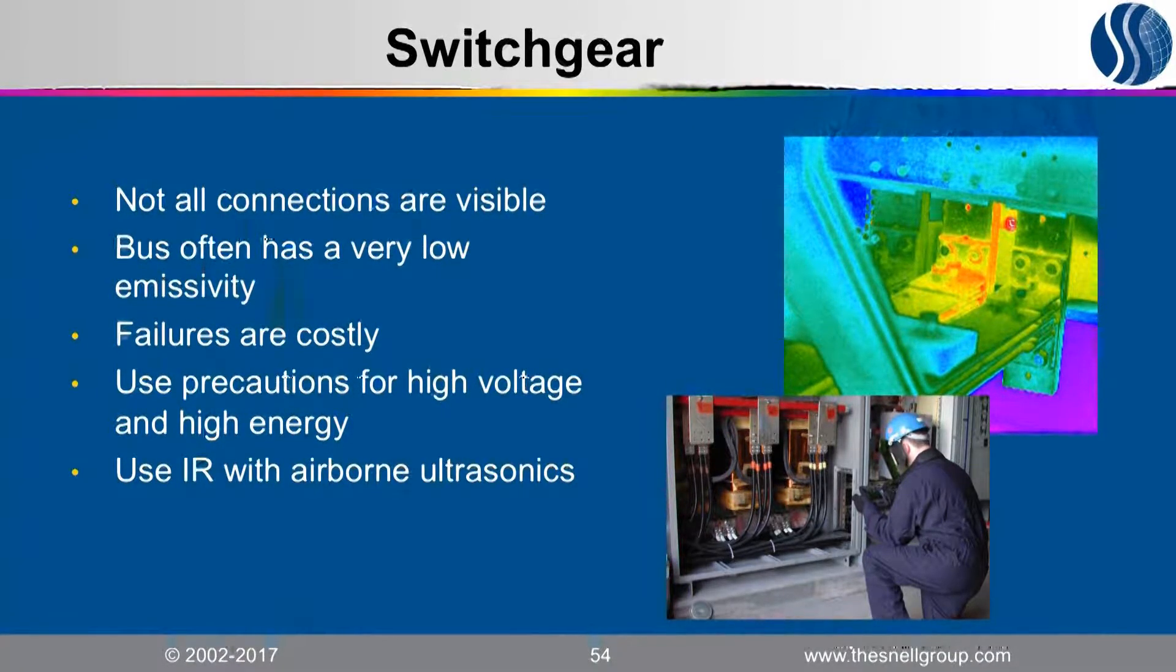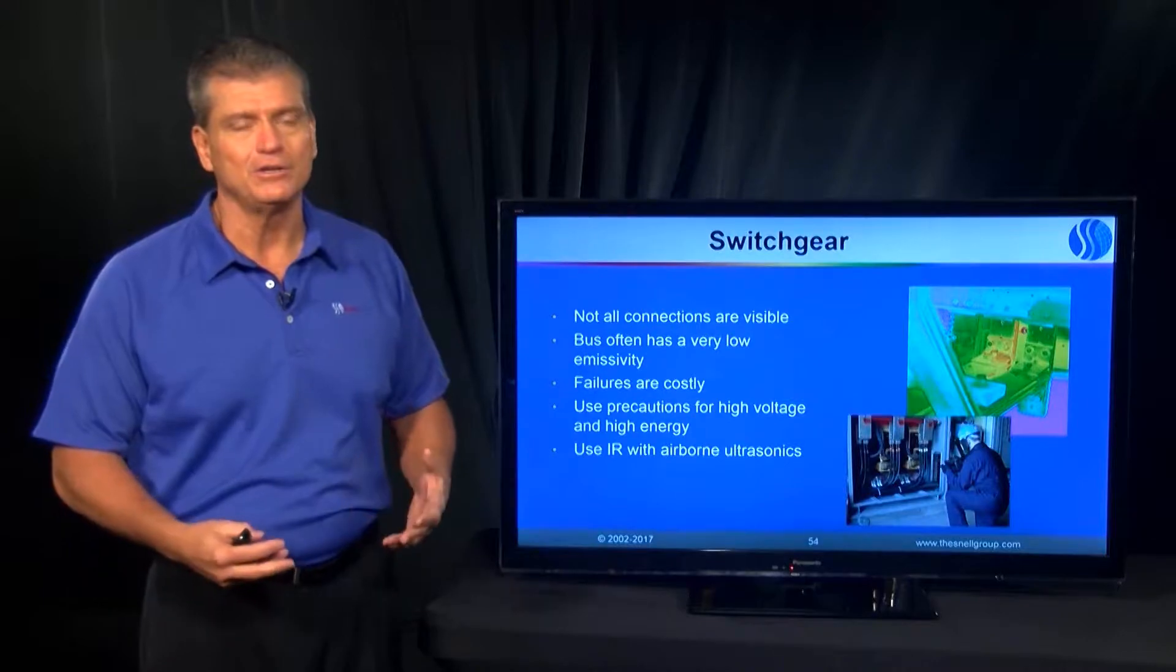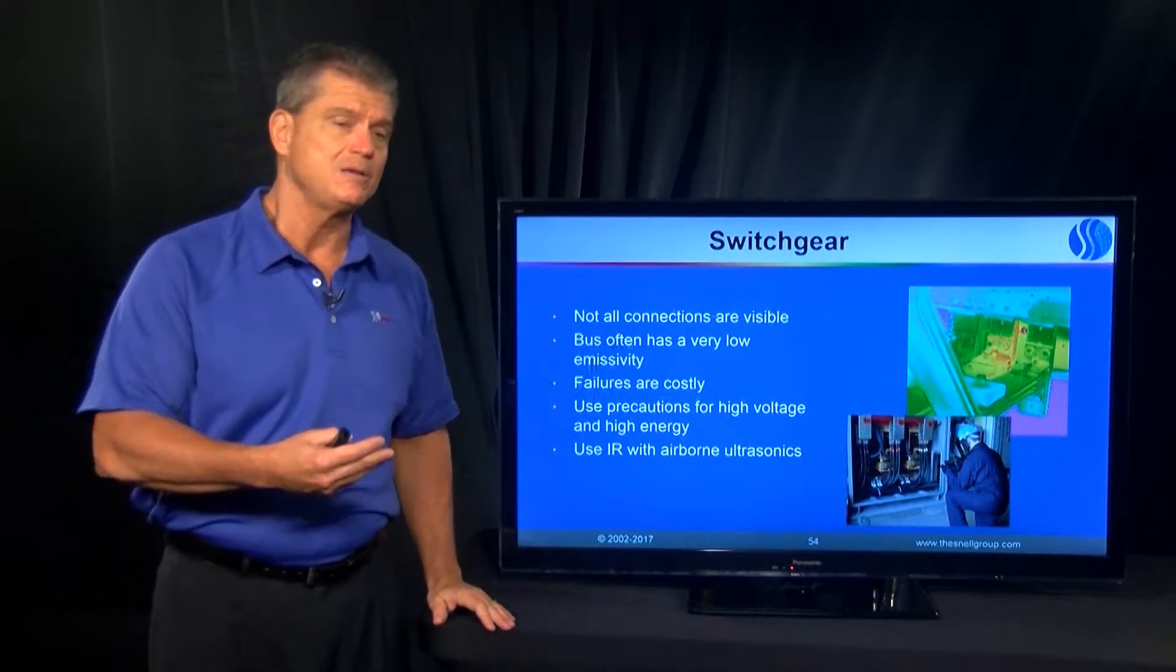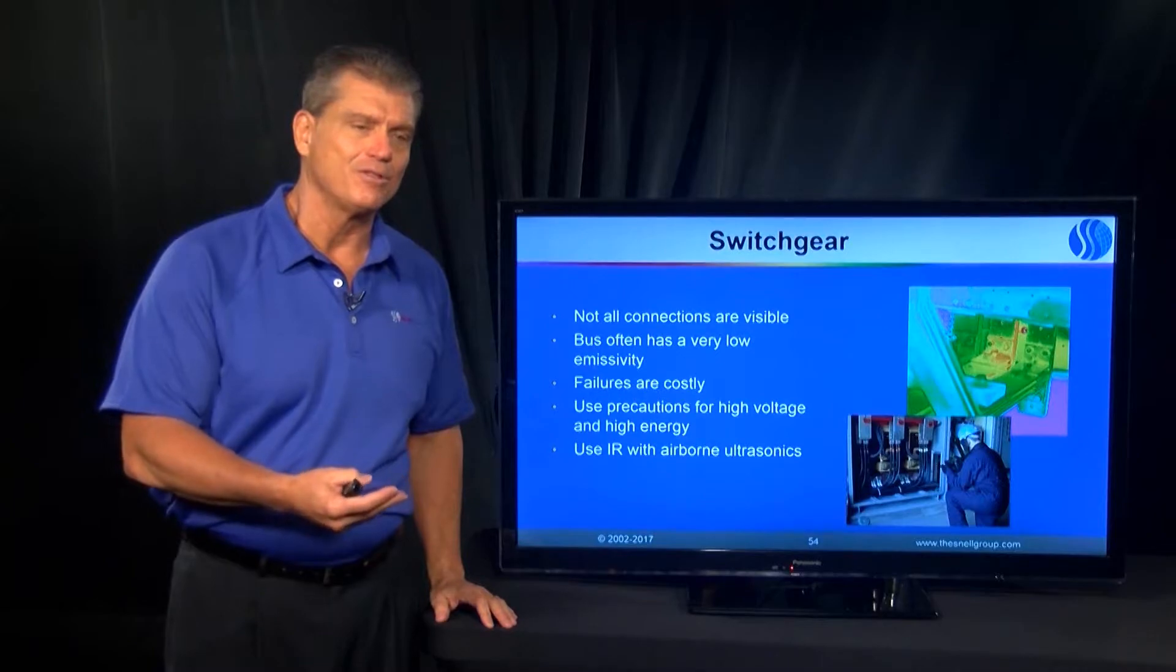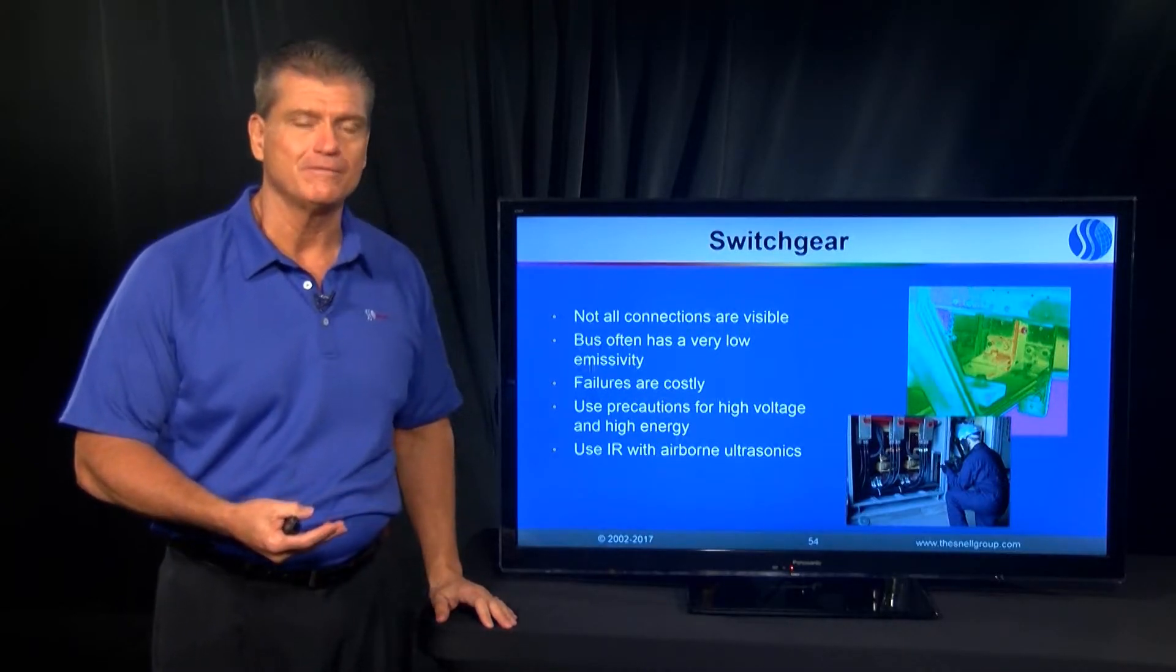Bus has a very low emissivity, so even if I can get a good look at it, I'm challenged by the fact that it does not emit the heat or the thermal patterns that I'm looking for readily.